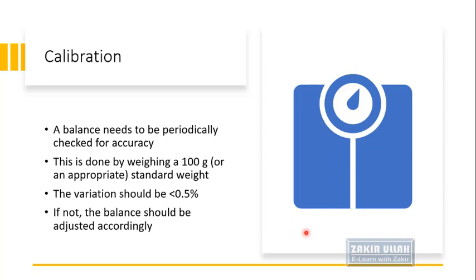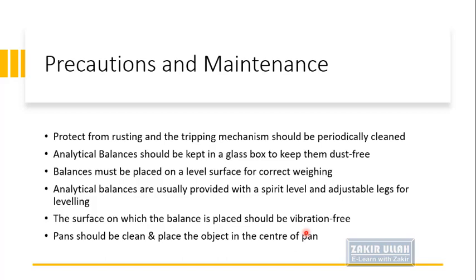Balances need to be periodically checked for accuracy through calibration. Calibration is done by weighing a 100-gram standard weight or another already known weight. The variation allowed should be less than 0.5 percent. If the variation is more than 0.5 percent, the balance should be adjusted accordingly.